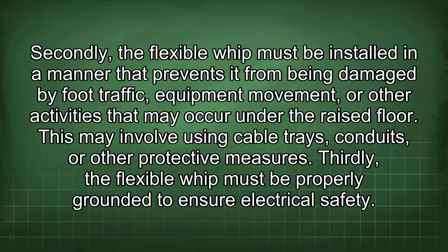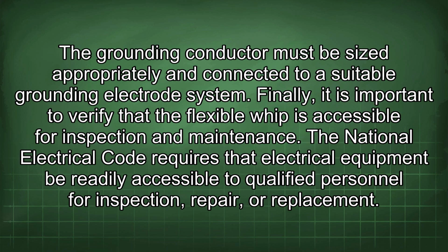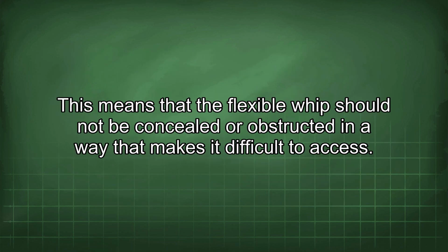Thirdly, the flexible whip must be properly grounded to ensure electrical safety. The grounding conductor must be sized appropriately and connected to a suitable grounding electrode system. Finally, it is important to verify that the flexible whip is accessible for inspection and maintenance. The National Electrical Code requires that electrical equipment be readily accessible to qualified personnel for inspection, repair, or replacement.